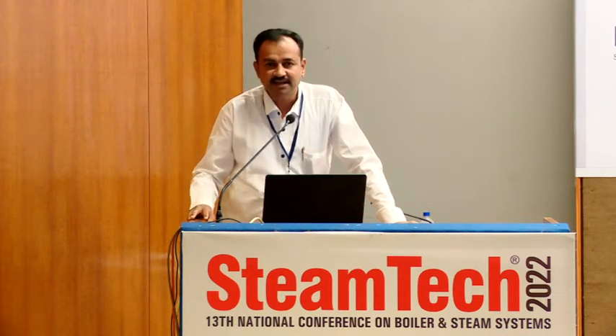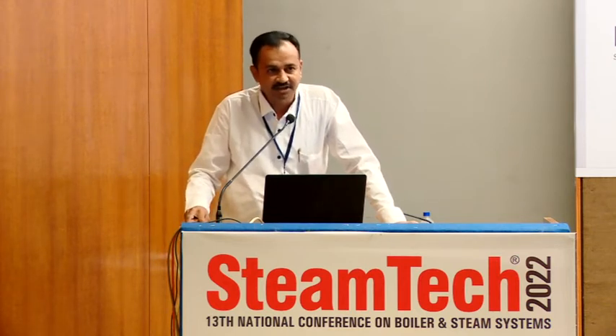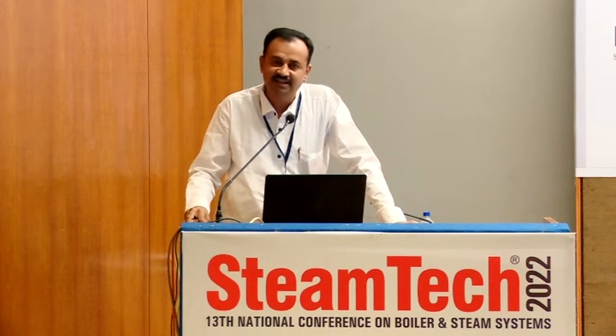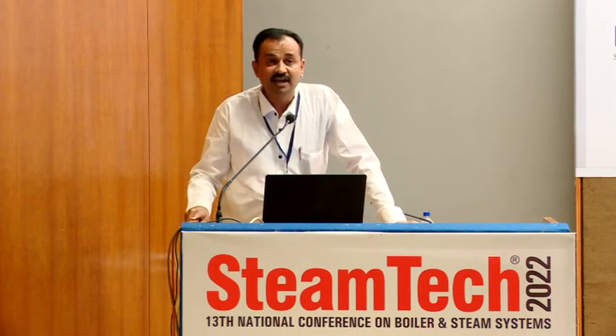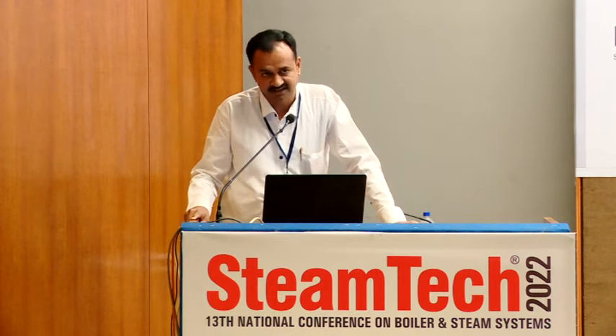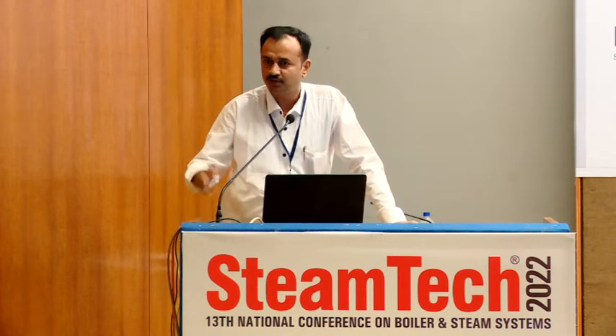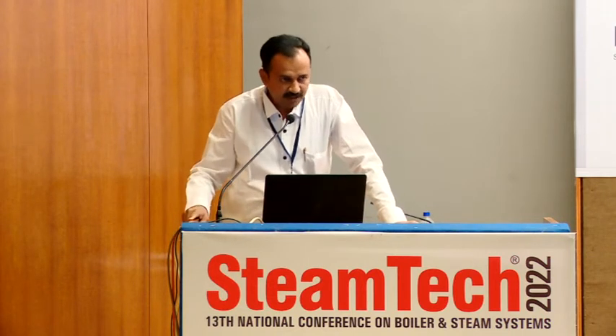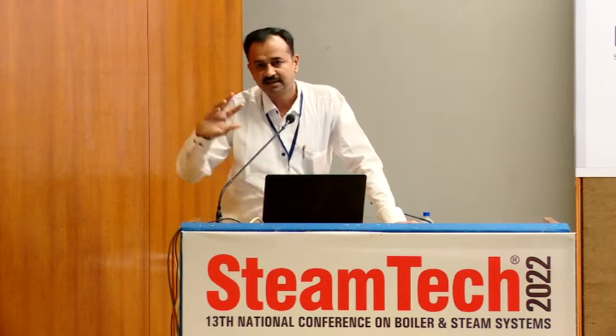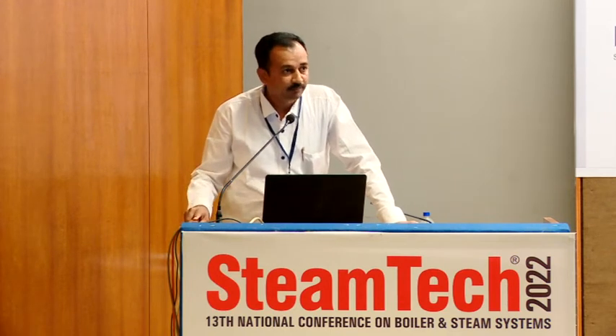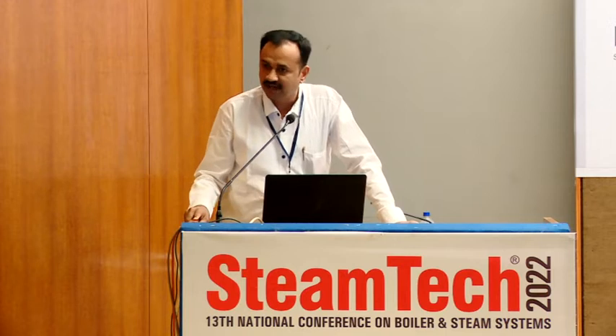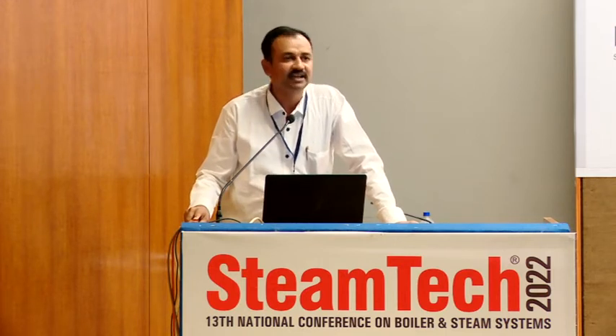So this gives us the trigger for what we should do to optimize the boiler house energy. That gives the direct trigger about optimizing the efficiency of the boiler or the fired furnaces. I will not go into the equations that you know very well. The boiler thermal efficiency, directly, is the percentage of the heat input burnt inside the furnace which is utilized to generate the steam at the outlet side. That is the direct efficiency.